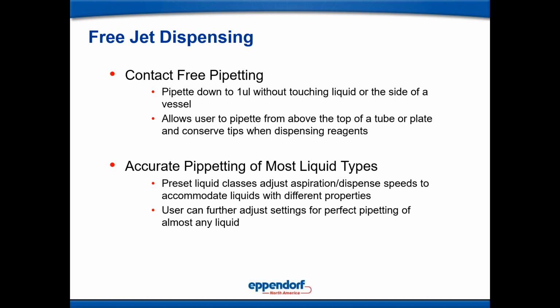When you're pipetting ethanol, the machine will even pre-wet the tip, pull liquid up the tip and spit it back out. What that does is it saturates the airspace above the liquid column and prevents that expansion from causing the liquid to drip or pop out of the machine. So that's why our machine is exceptionally well designed: it uses every benefit we can by engineering it to work specifically with different types of liquids and still get a good result.